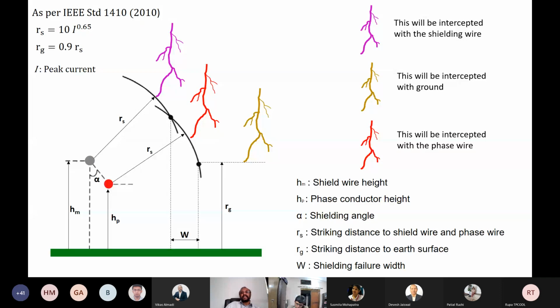Now you will understand that when we are designing direct lightning protection for medium voltage lines with a shielding wire, we have to make sure that the width W, which is called the shielding failure width, should be as small as possible. Okay, it should be as small as possible. So I'm not going into the design criteria of this. I'm just giving you the basic idea.